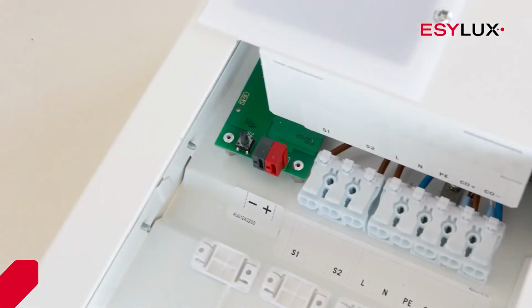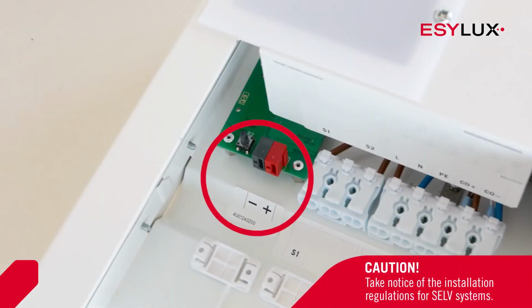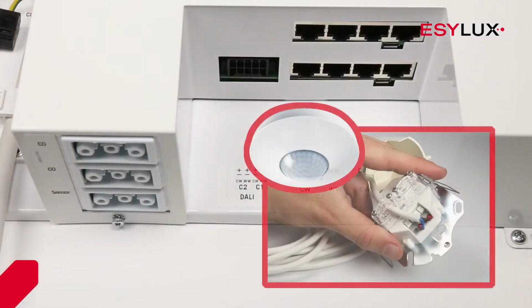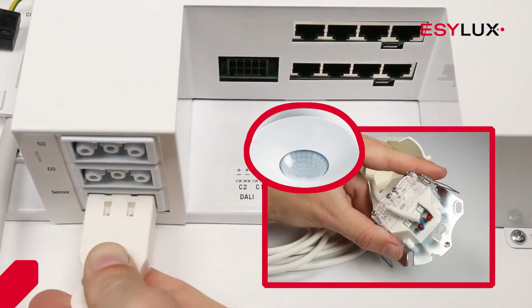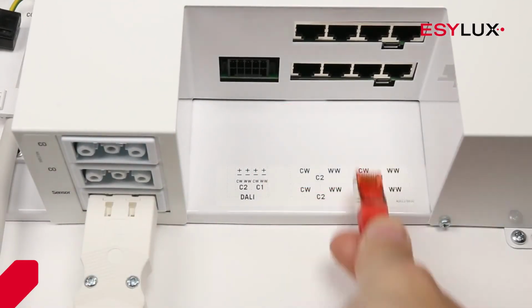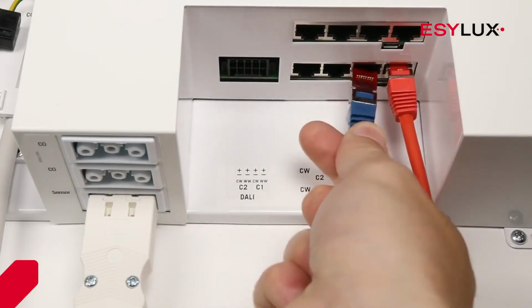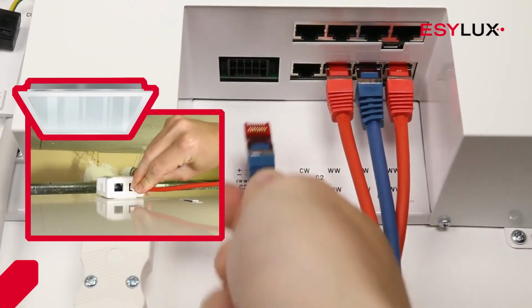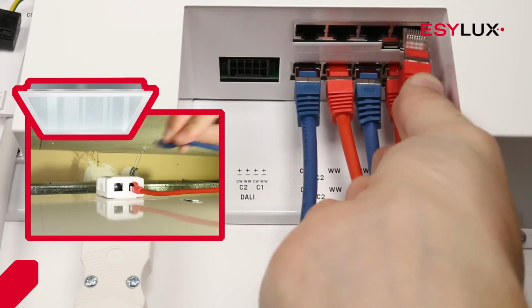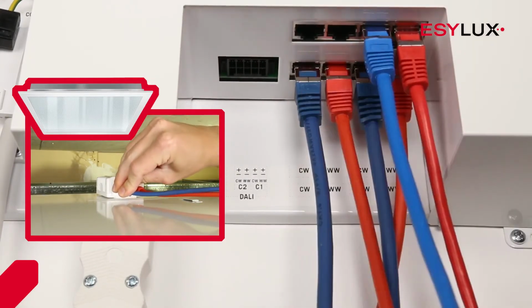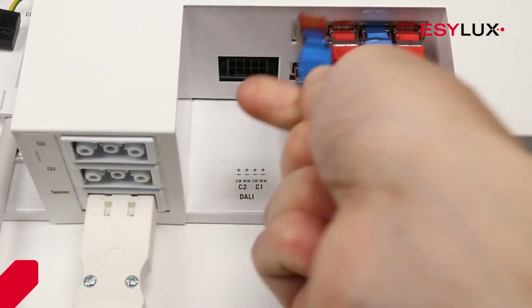If you are using a KNX variant, you can network the SmartDriver with the KNX bus via the left-hand socket. It is very easy to connect the presence detector via the sensor interface. The lights are connected to the SmartDriver using the RJ45 cables. The RJ45 interfaces are assigned channels that the SmartDriver can control separately.